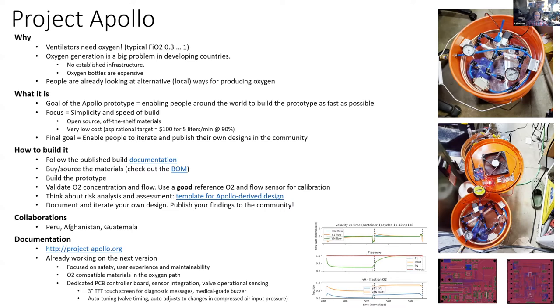We have fairly sophisticated simulation software and a number of designs for hardware and software control boards. We are now iterating towards adding user experience improvements: a three-inch touchscreen for diagnostic messages regardless of the language the device is intended for, a medical grade buzzer, and most importantly, an auto-tuning process in software so the device itself will adjust valve timings to work with variable changes in compressor air input pressure.